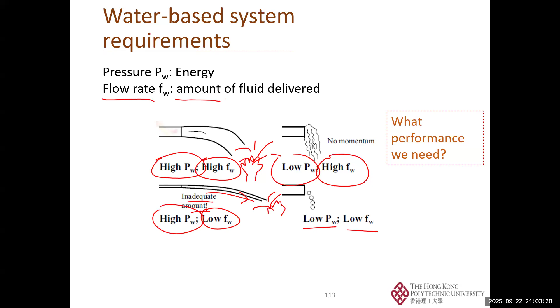We further have pump heads to allow water to be delivered from low level to high level. From the ground floor transfer tank, we need the duty pump and standby pump to transfer water to upper floors. In some cases, if the topmost hydrant or FS inlet is higher than 60 meters, we need an intermediate booster pump to help pump water upwards to higher levels.